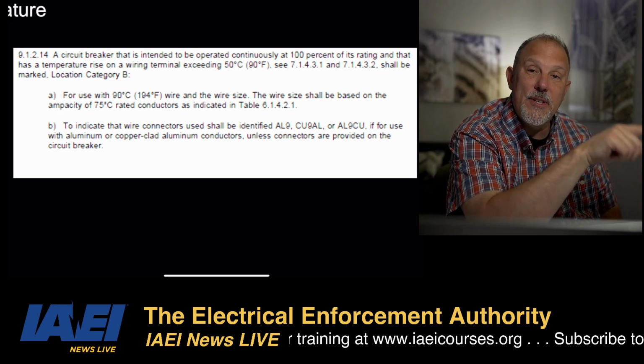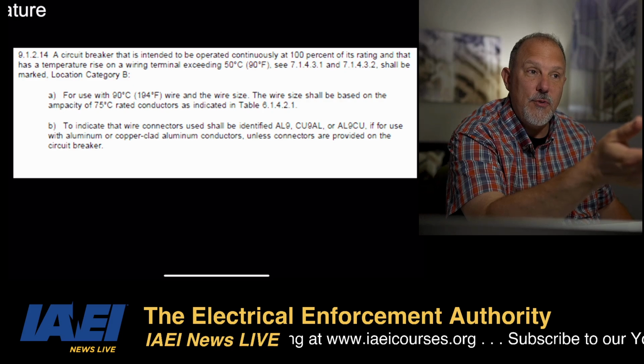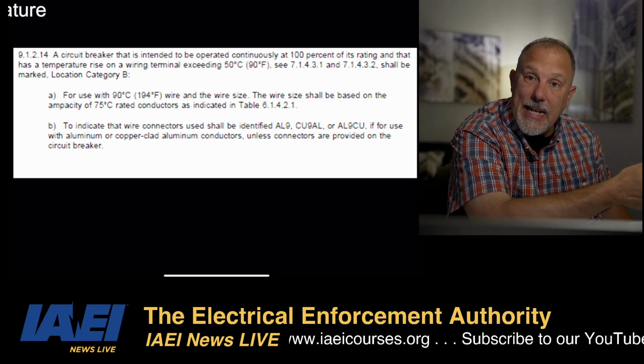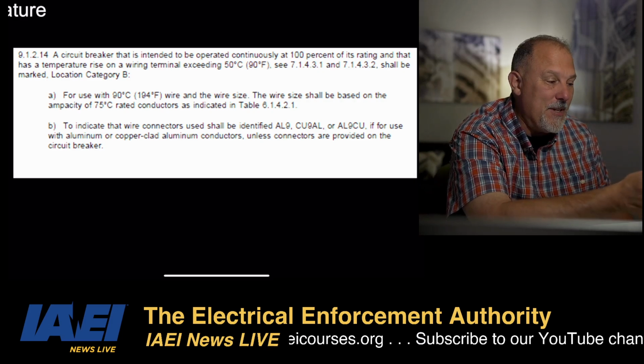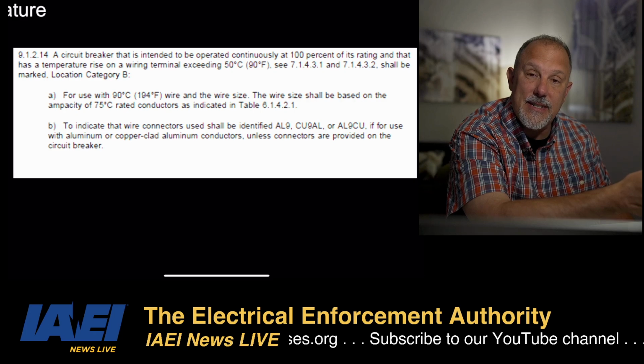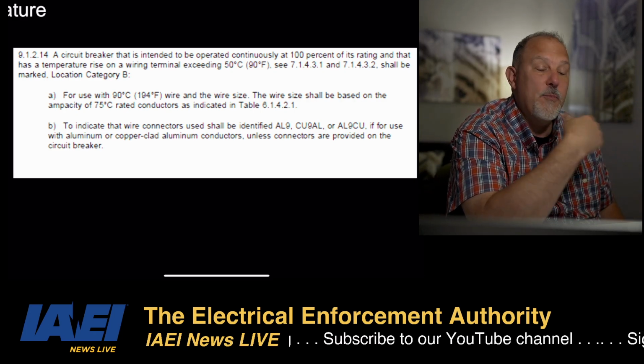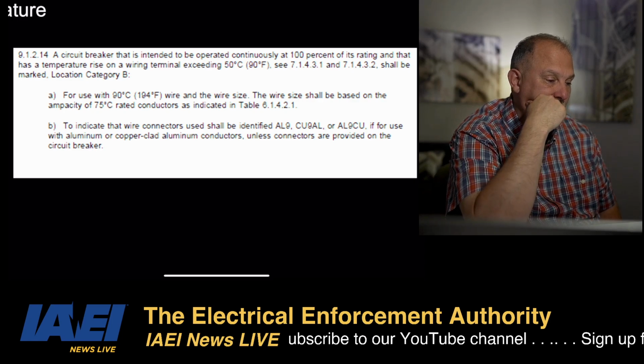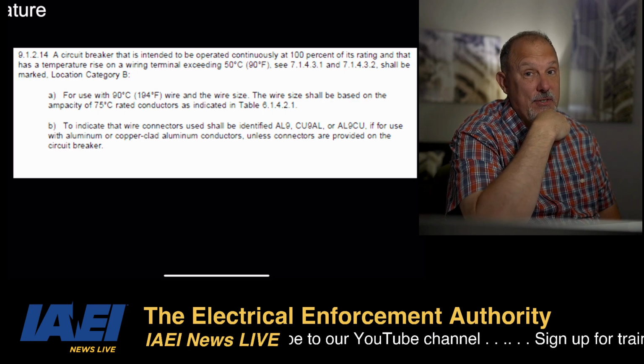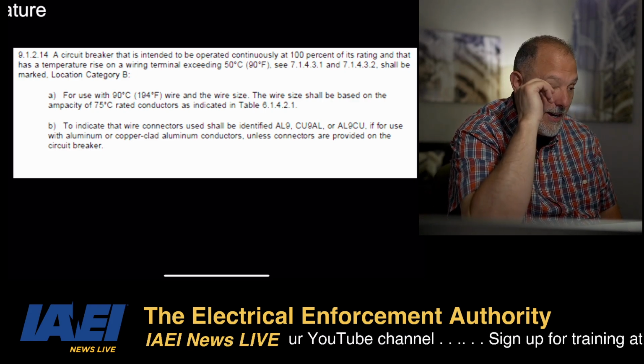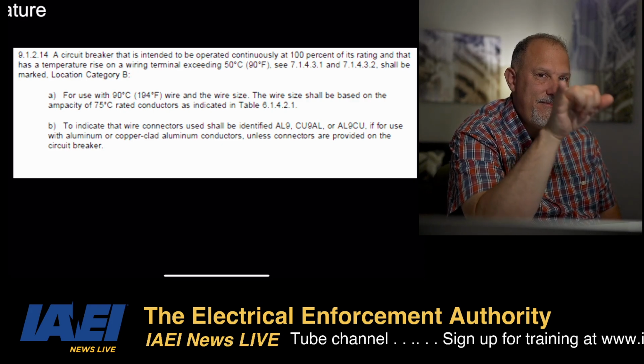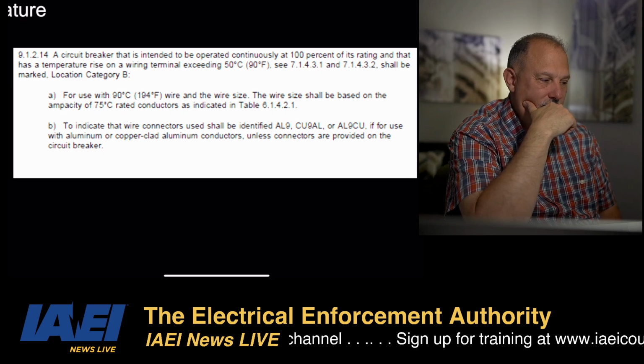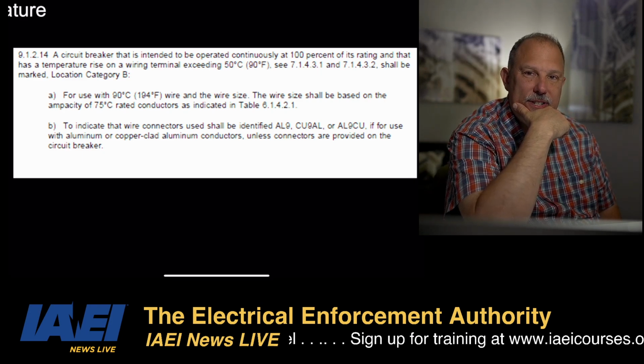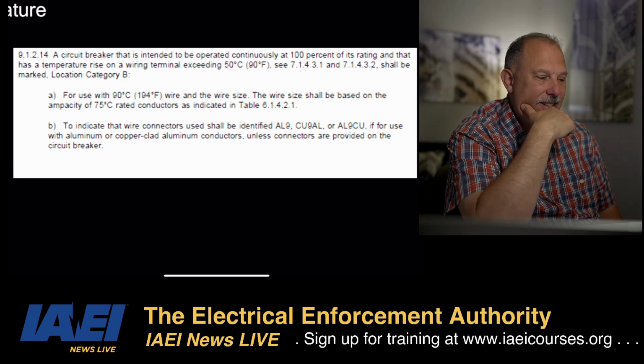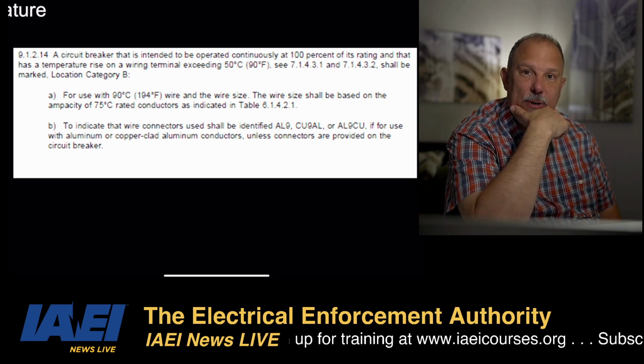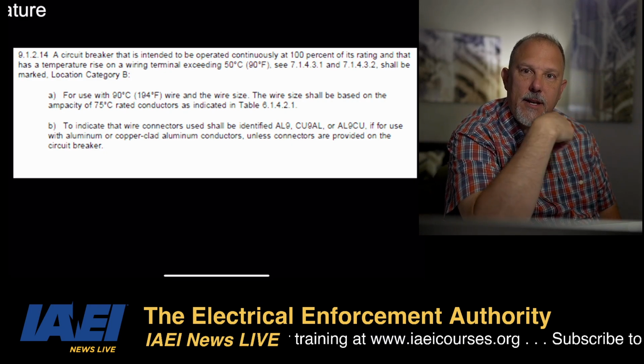The reason that note is on there is not for when you're doing an 80% rated application. The only reason you have to use 90 degree C insulation is when you're using it at 100% of its rating. Tell me that's not an interesting one. I've got to go find that email now. I love these moments. Don't you just love these moments? You realize at some point in time that you never stop learning.